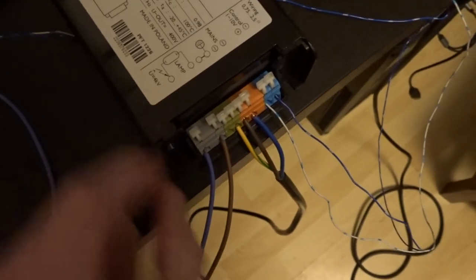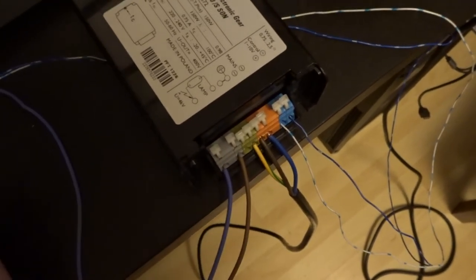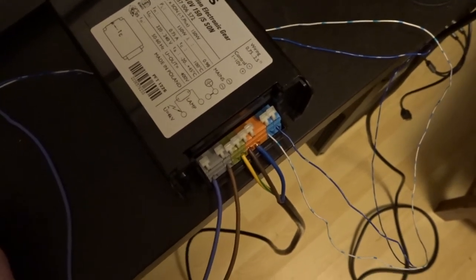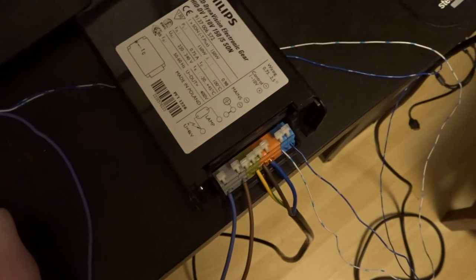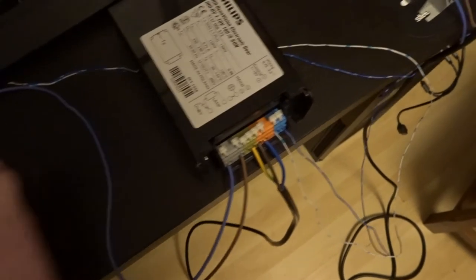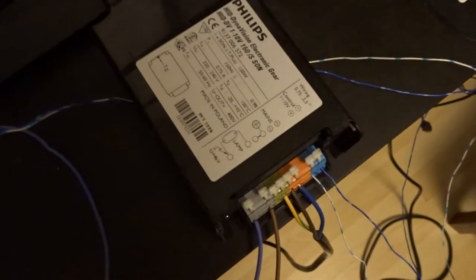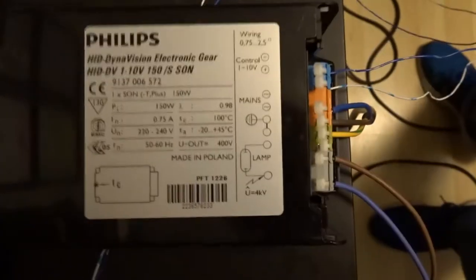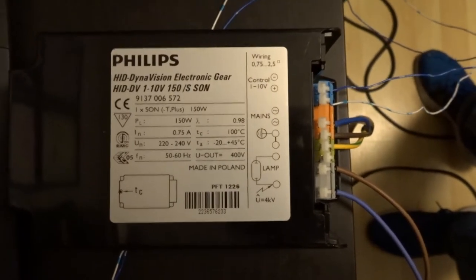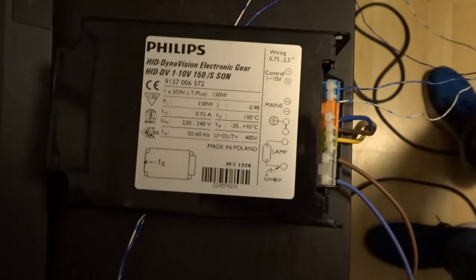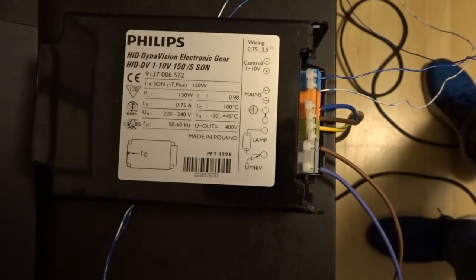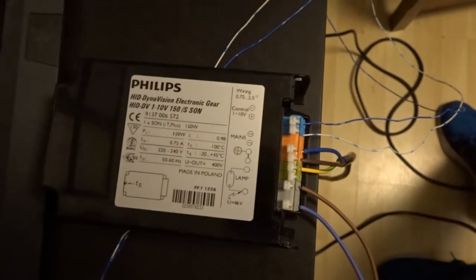And you've got your output. It's got a high starting voltage with a few thousand volts to strike it up. And then once it's striked the gas is conductive and it can go down to normal operating voltages. But this is a Philips HID DynaVision. You can get DALI ballast as well, which is digital addressable lighting interface. I'll have a separate video on DALI stuff later.